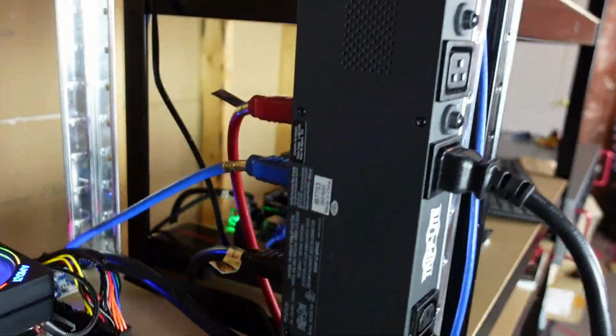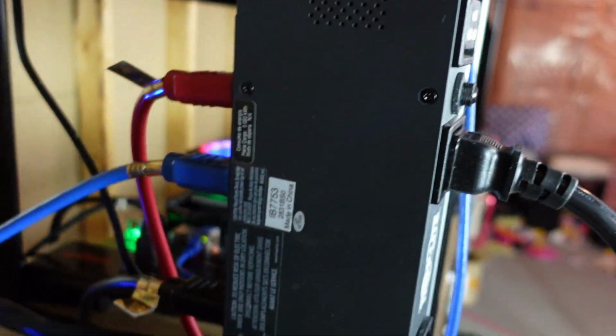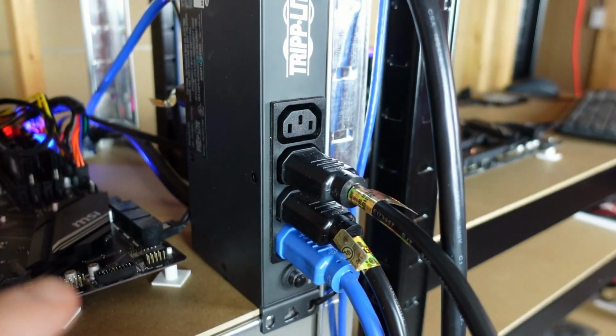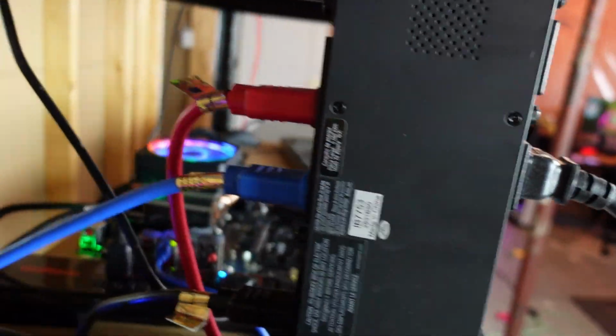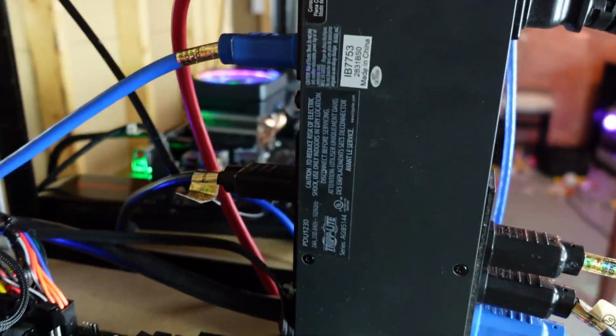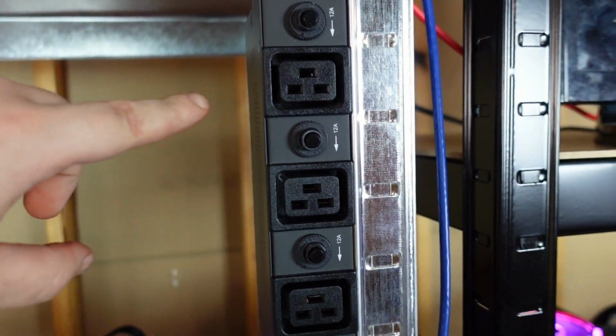And we have a lot more room on our PDU here. If you're unaware how this PDU operates, I have a four bank of C13, and on the back I have three four banks of C13. And then I got separate banks of four here. So each one is on their own breaker of 12 amps.